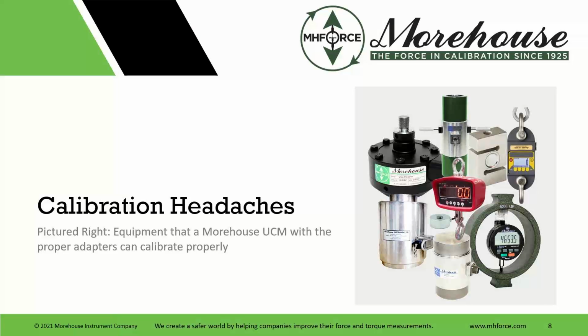So, headaches. One of the major headaches is customers. You start a force calibration lab and customers want to send you stuff, and you want that stuff because you just invested in equipment and you want to make money on that equipment. But when they send you stuff, you might not have the right adapters to calibrate it. And now that creates a dilemma. We've been in this business for over 100 years, and we still see instrumentation come in today where we do not have the adapters. A lot of times that's not the case anymore for force. It's more so for torque that we do as well, though it's still for force. Someone makes a new load cell, a different thread that we haven't seen before, a new widget, and we need to figure out how to calibrate it.